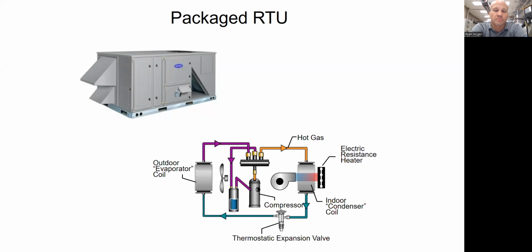So usually these are mounted on the roof, but it doesn't have to be on the roof. Sometimes we mount them on the ground, and then we duct them into the side of the building for various reasons. Maybe the roof is really, really sloped, or maybe the roof can't bear the weight of the rooftop because it's not designed that way. So we might mount them on the ground, but usually they're mounted on the roof to keep them out of the way, save parking space, have them be serviced on the roof where they don't interfere with any of the occupant usage of the ground, although it sucks from a service guy standpoint, but that's typically where they're at.